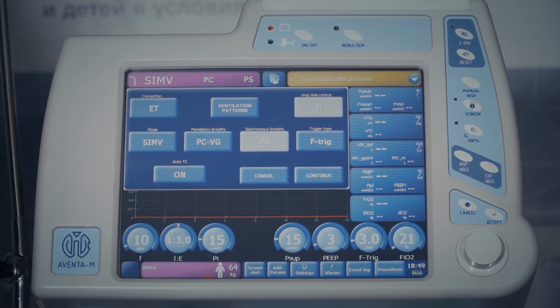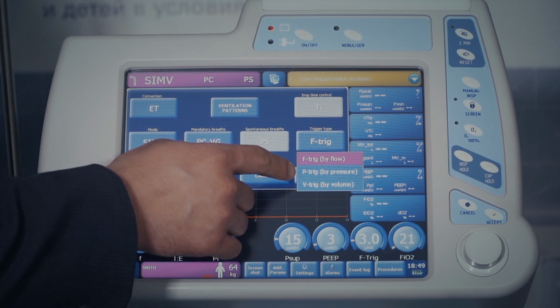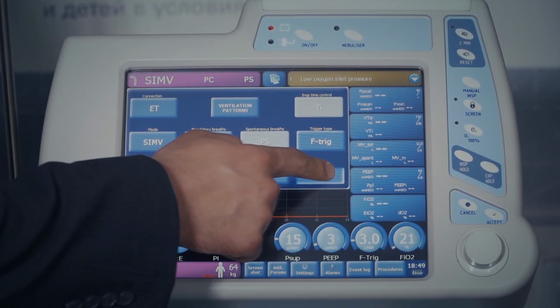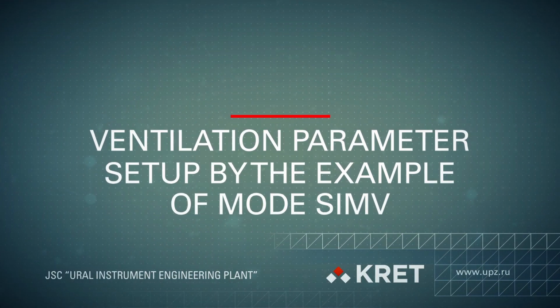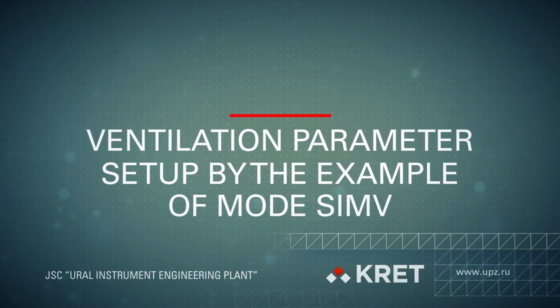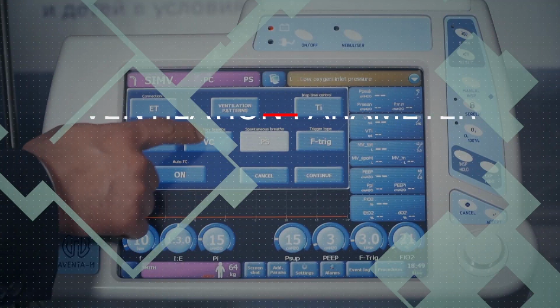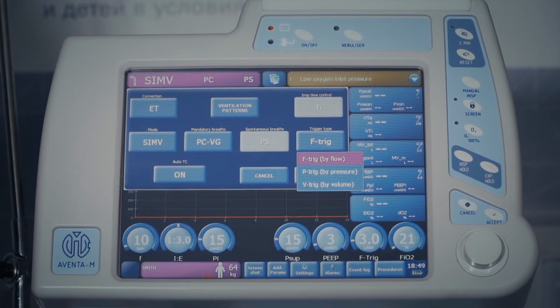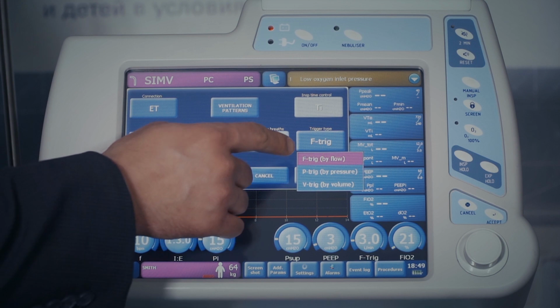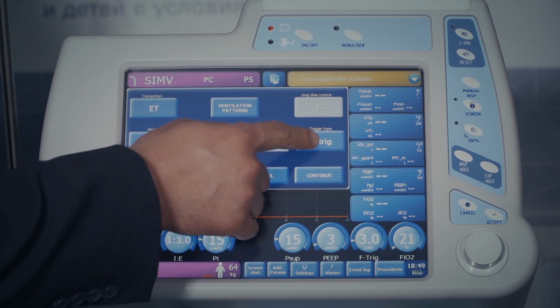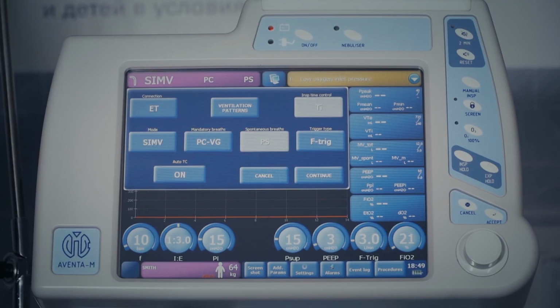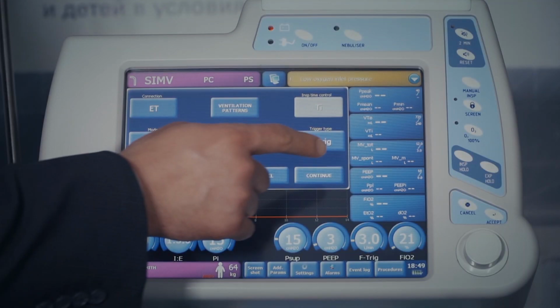Besides, it is possible to use previously saved ventilation parameters prepared for different medical cases by pressing button Ventilation Patterns. After selecting the corresponding parameters, press button Continue. When a new ventilation mode is selected, its indicator will be displayed in the upper left corner of the screen. To change the ventilation mode, press the indicator of the current ventilation mode. Make the required changes and press button Continue.